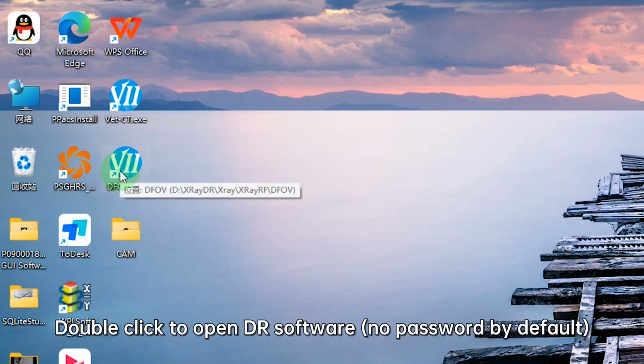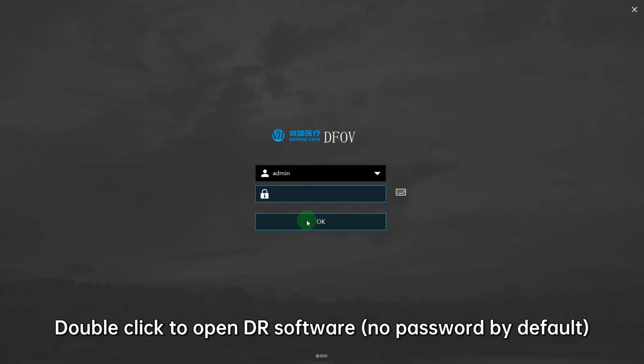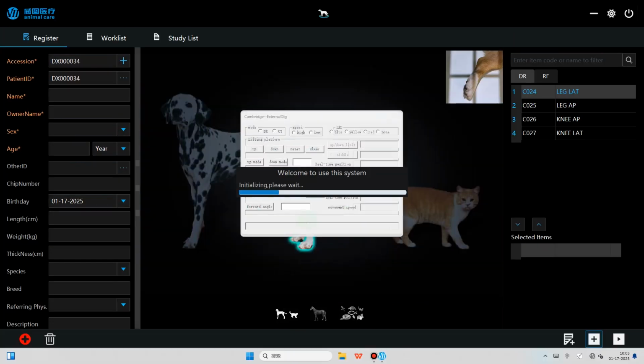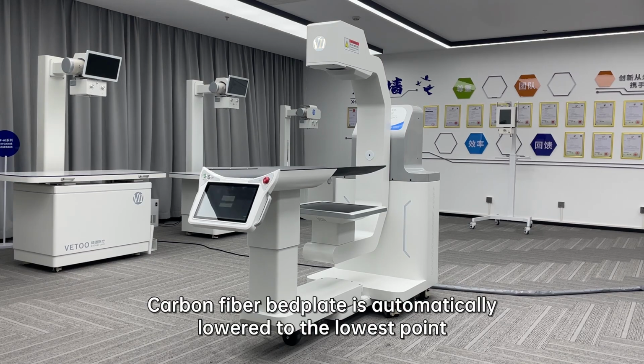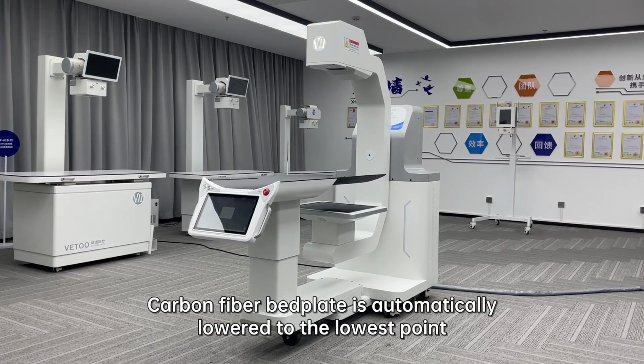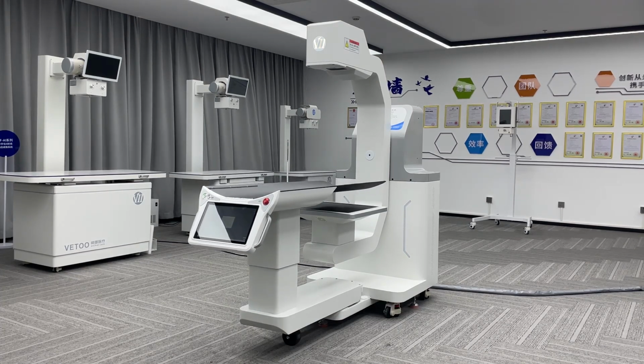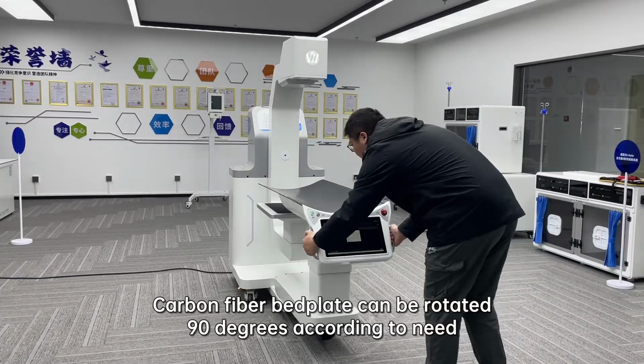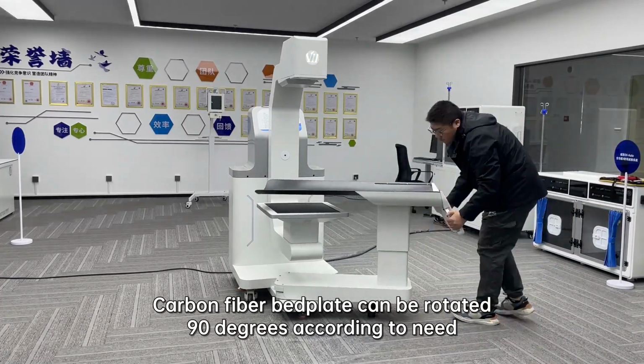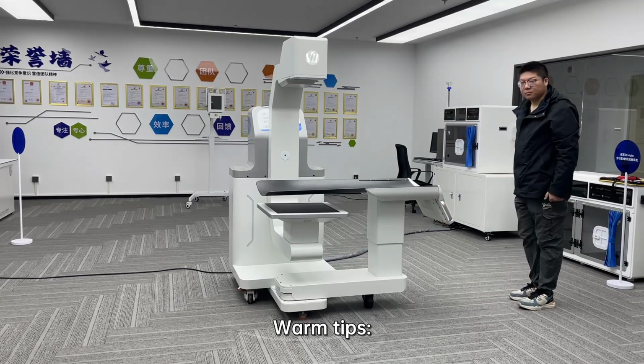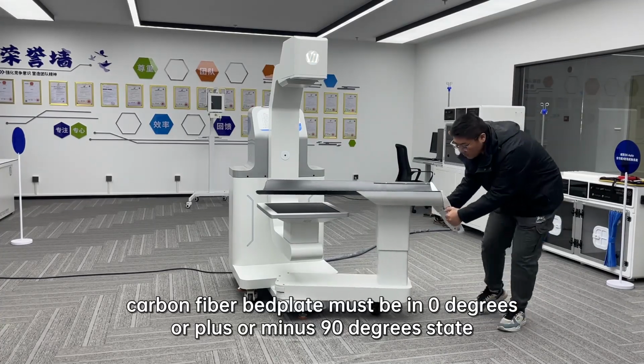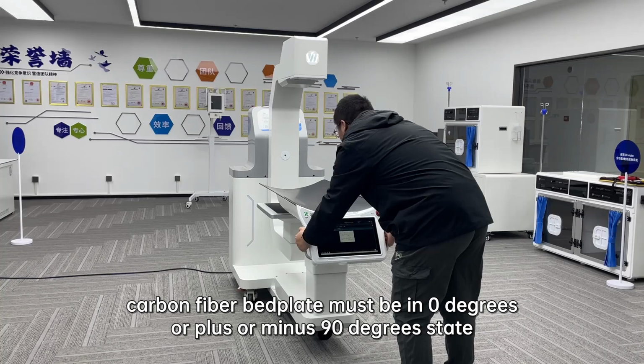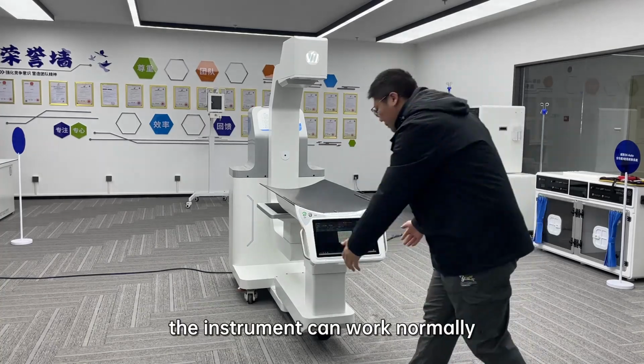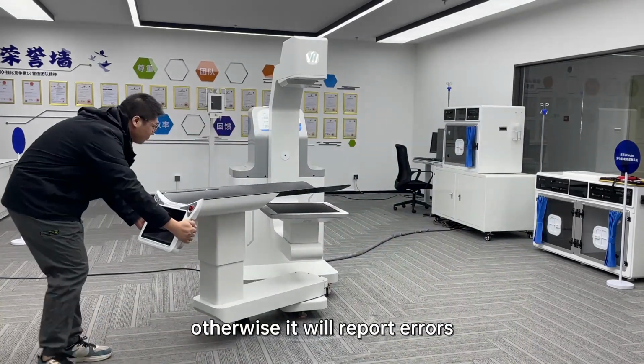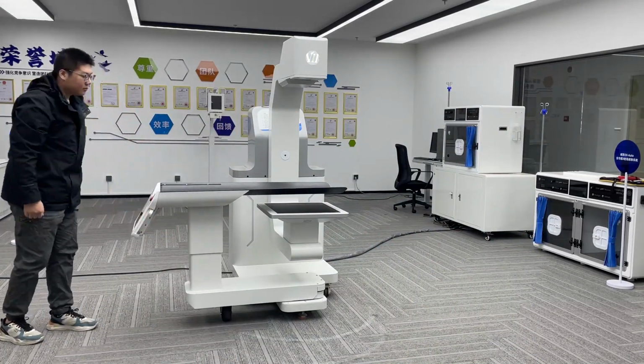Double-click to open DR software. No password by default. Carbon fiber bed plate is automatically lowered to the lowest point. Carbon fiber bed plate can be rotated 90 degrees according to need. Warm tips. Carbon fiber bed plate must be in 0 degrees or plus or minus 90 degrees state. The instrument can work normally, otherwise it will report errors.